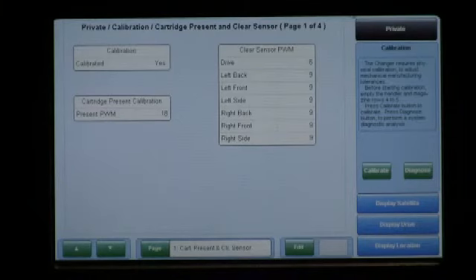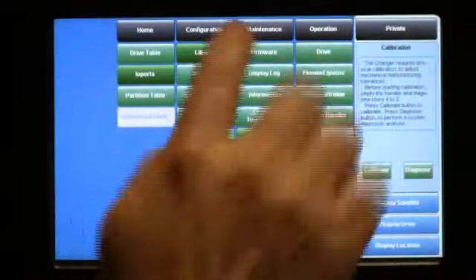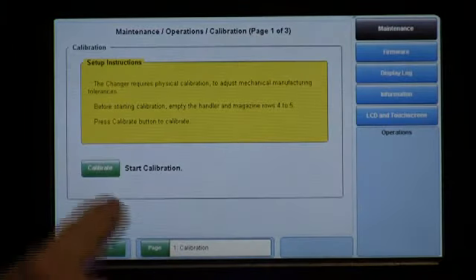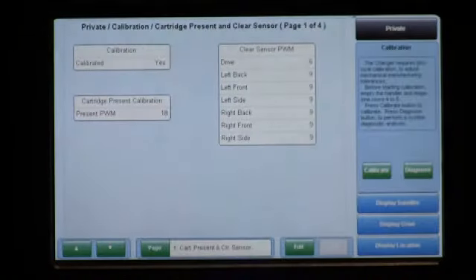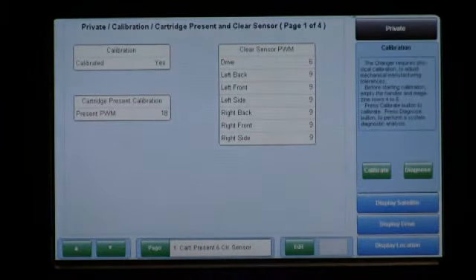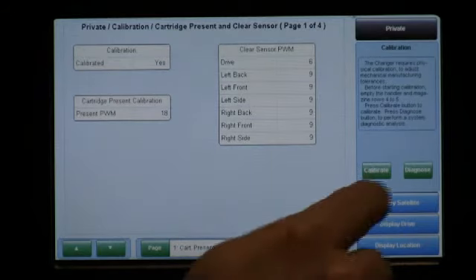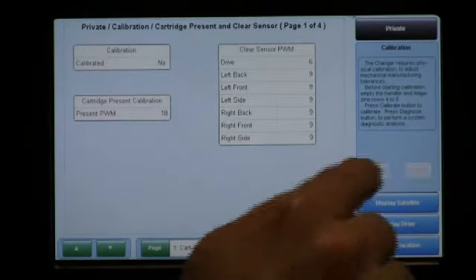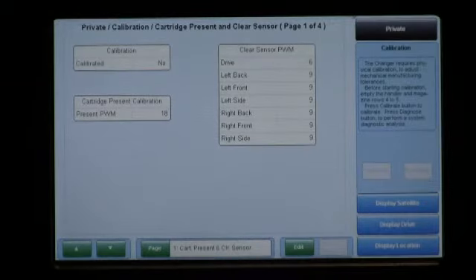Once the appropriate tapes have been removed from the magazines and the magazines have been installed back into the library and into the locked position, you're ready to proceed with the calibration. Depending on which screen you're in, you can either be in the maintenance operation screen and the calibrate button is here, or you could be in the private calibration screen and the calibrate button is here. In either scenario, select the calibrate button. This will start the calibration process.